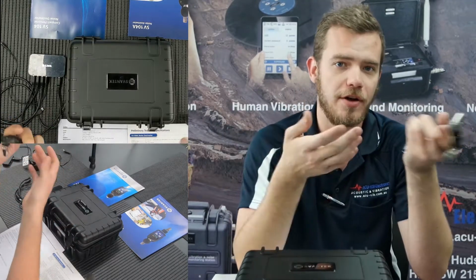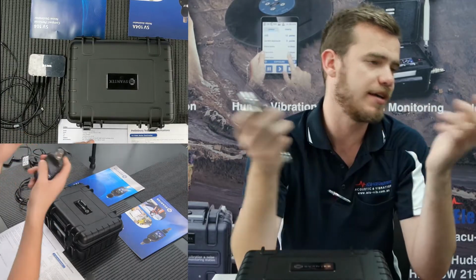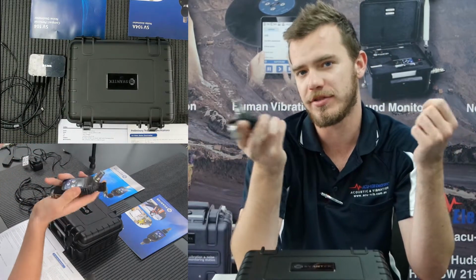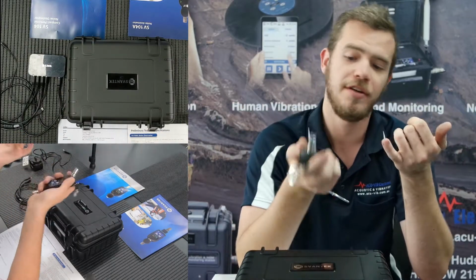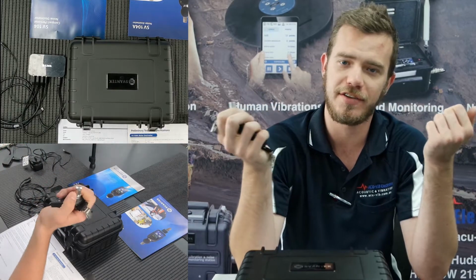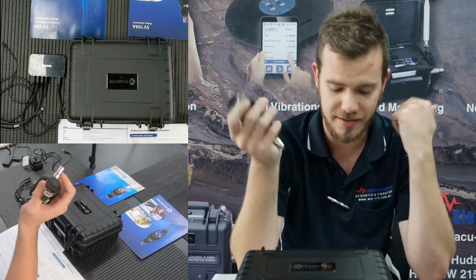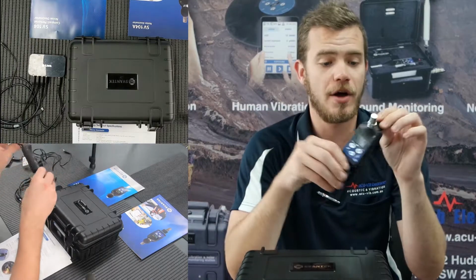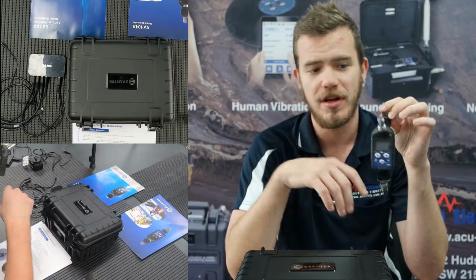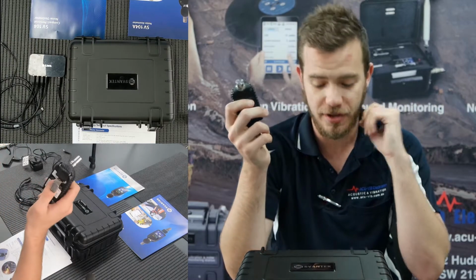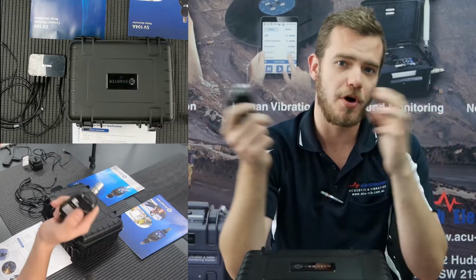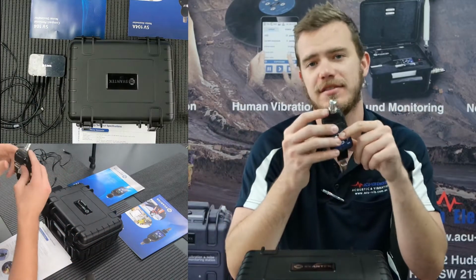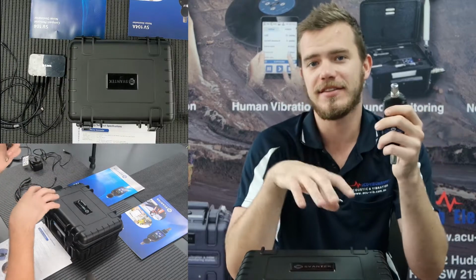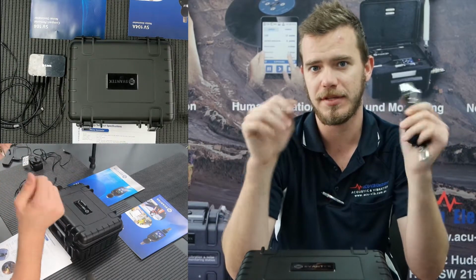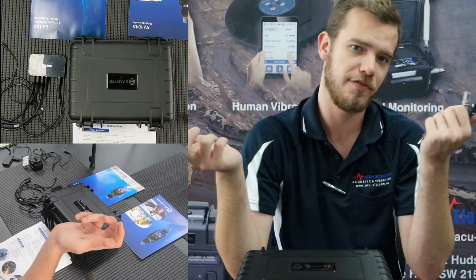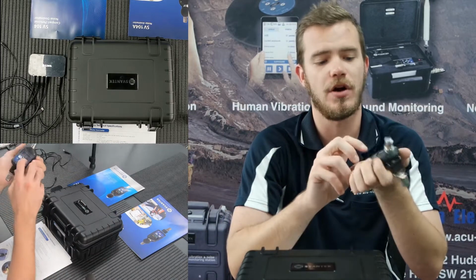So at Acu-Vib, we're a full NATA calibration lab. We calibrate all instruments, all noise dosimeters, and we often run into microphone drift, microphone acoustic failure, and battery replacement as situations which we come across. Now, in regards to the SV104s, these microphones have a lifetime warranty on them. So if they get damaged, not by physical damage, then they will replace the microphone free of charge. I've never had to send one back to Svantek for a replacement, though they've only had to replace tens of them out of the thousands that have been sold around the world.